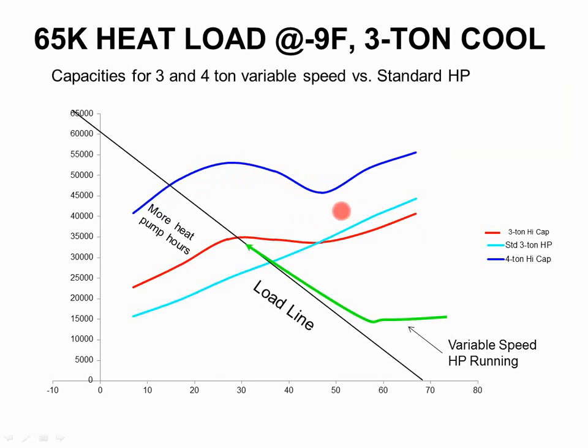Right? Now the first thing you notice about these variable speed ones is they're not straight lines. The standard heat pump is basically on, doing his thing, and that's it. The variable speed heat pumps can change the speed of the compressor, the condenser, the indoor fan, the metering devices, and 50 other things they can control. We're able to maintain those higher discharge temperatures and higher BTUs. There are some weird quirks that dip down in there because of the airflow I need for a required amount of refrigerant, but for the most part, the line's a little bit more horizontal, and then eventually it does fall off.